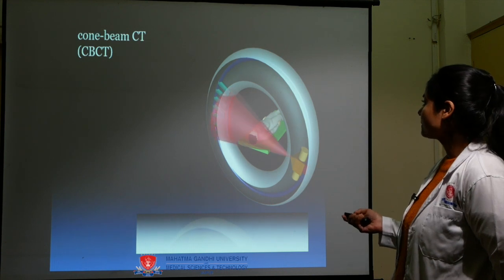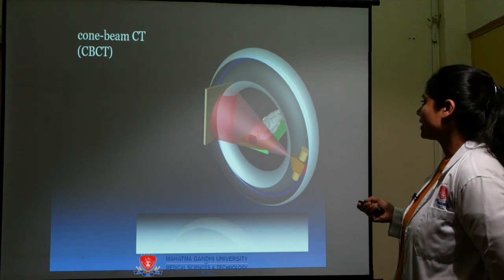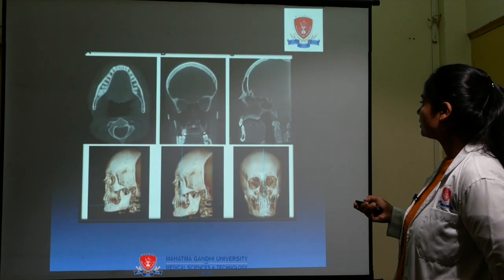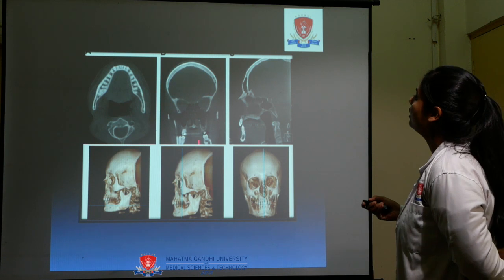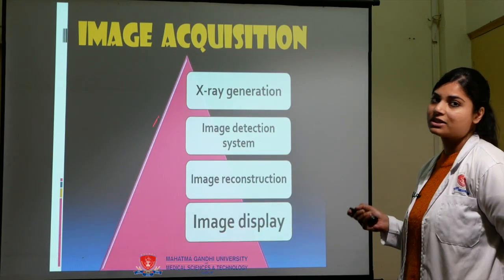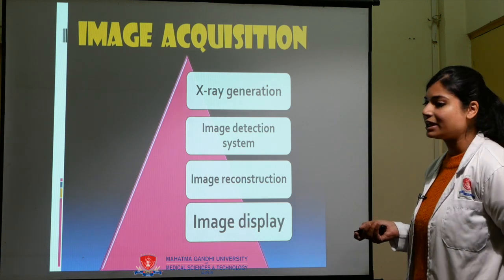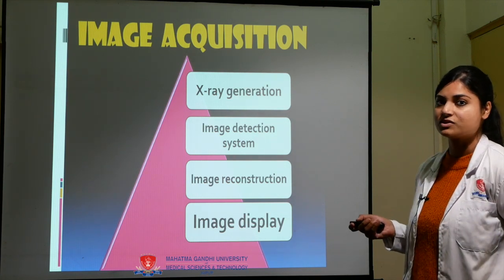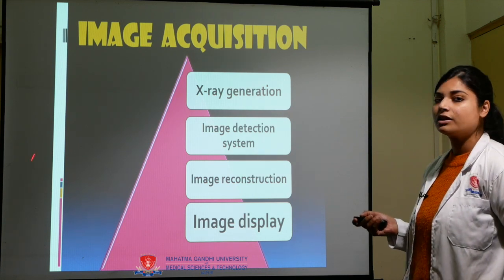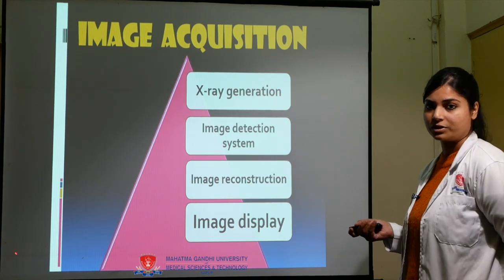This is a cone beam CBCT unit showing the X-ray source, cone beam, and flat panel detector attached to the gantry to capture the image. The CBCT captures data in different planes: the axial plane, coronal plane, and sagittal plane. Image acquisition occurs in steps: first, X-ray generation in a cone beam; then image detection on the flat panel detectors attached to the gantry; then image reconstruction with the help of projection bases; and finally, image display on the computer as secondary reconstruction.